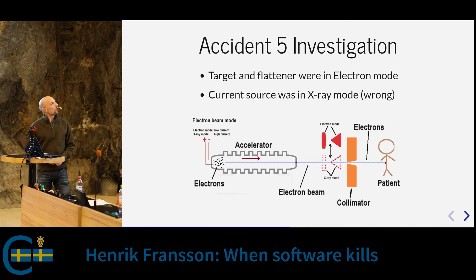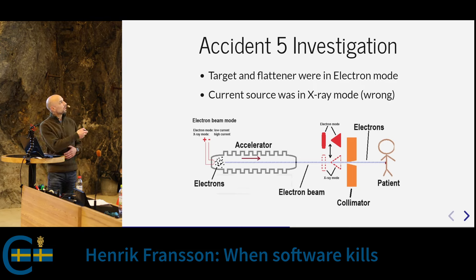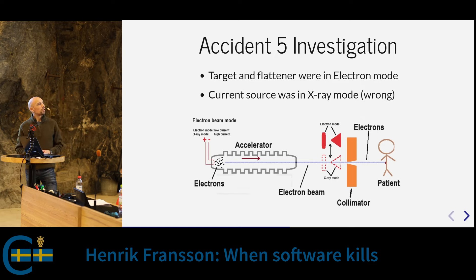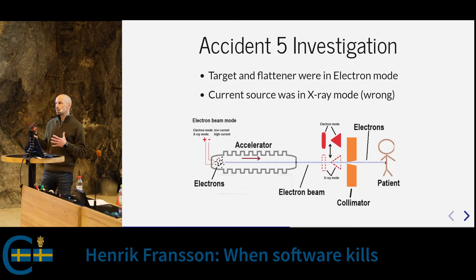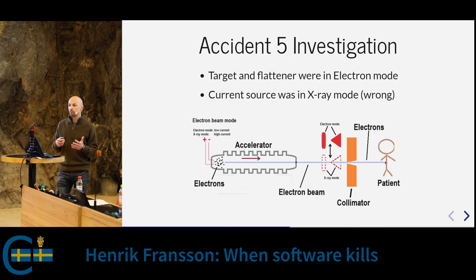Going back to the linear accelerator: the metal parts were out of the beam's path, but due to the race condition the electron gun current was set to the high setting instead of the required low setting — a hundred times too high. This happened because the move was not instantaneous and the subroutines used shared variables between them with no protection or thread safety implemented in the software.